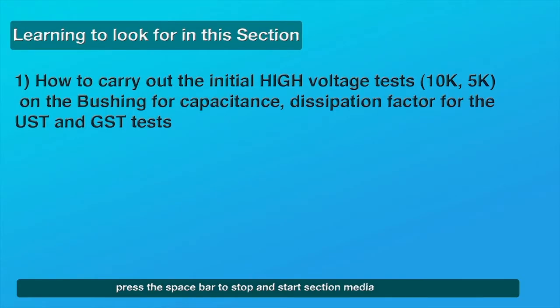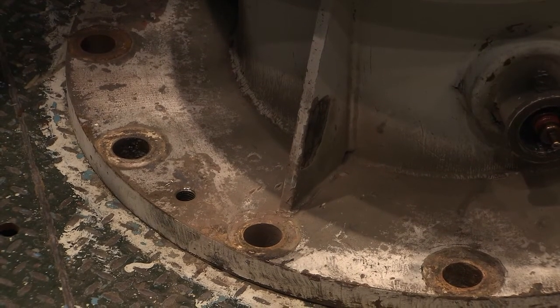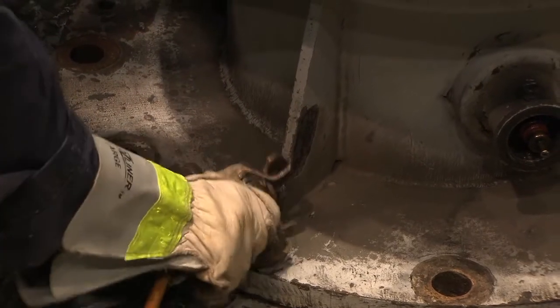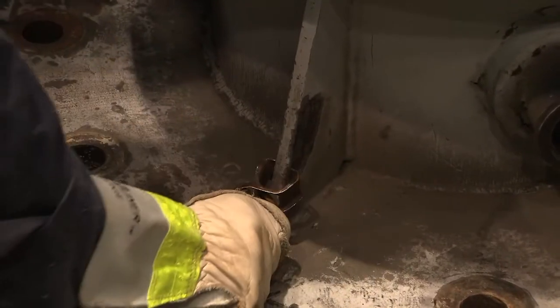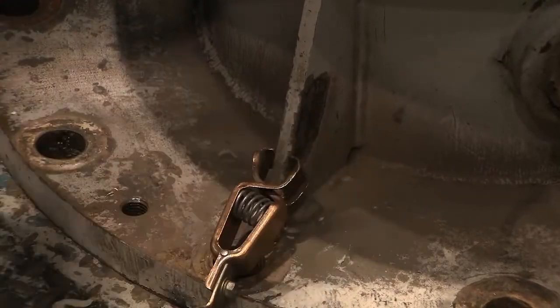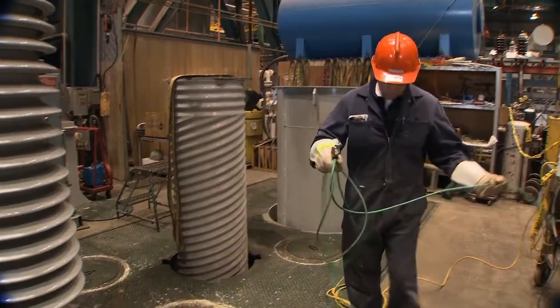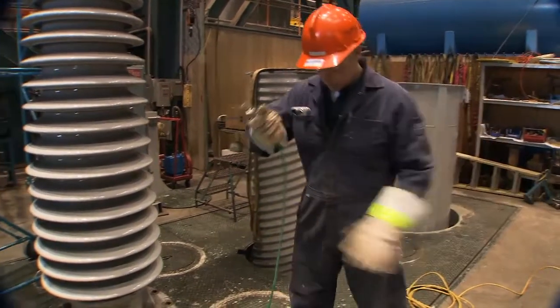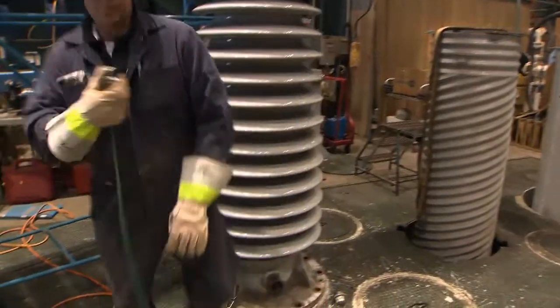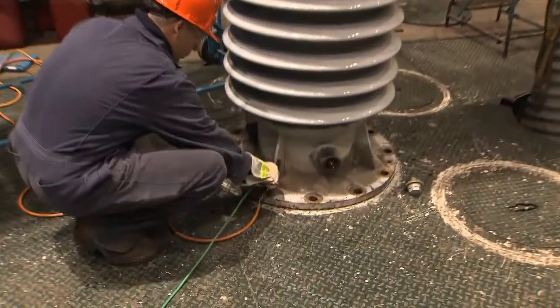Initial high voltage electrical tests for capacitance and dissipation factor. For the C1 test, begin by connecting one end of a ground cable to the bare metal of the flange and the other end to the ground rod for the building. Also connect the ground cable for the Biddle to the bare metal section of the flange on the bushing.